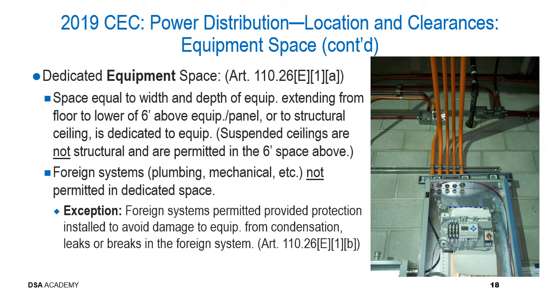This slide is devoted to the topic of dedicated equipment space, which, as we identified at the beginning of this presentation, is separate and distinct from dedicated working space. Dedicated equipment space is identified in the California Electrical Code, Article 110.26(E)(1)(a). It is basically defined as a space equal to the width and depth of the equipment, extending from the floor to the lower of 6 feet above the equipment or the panel, or to the structural ceiling, that must be dedicated to equipment. There's also a stipulation that suspended ceilings are not structural and are permitted within the 6-foot space above the panel or the equipment.